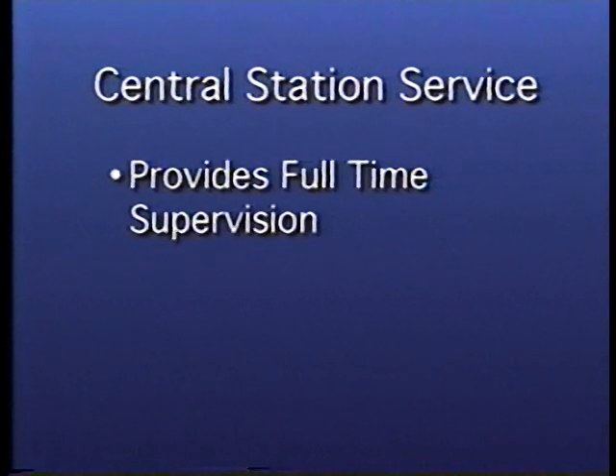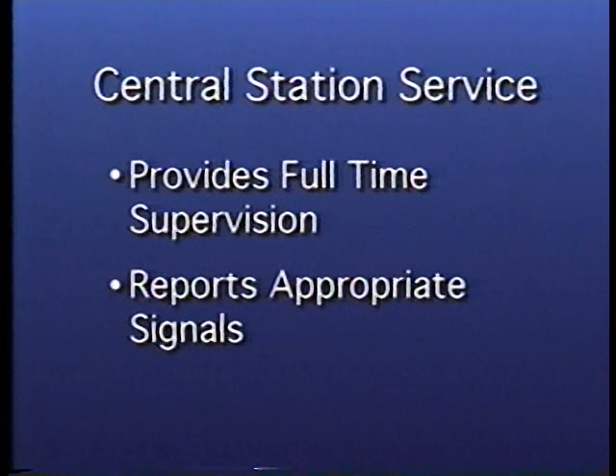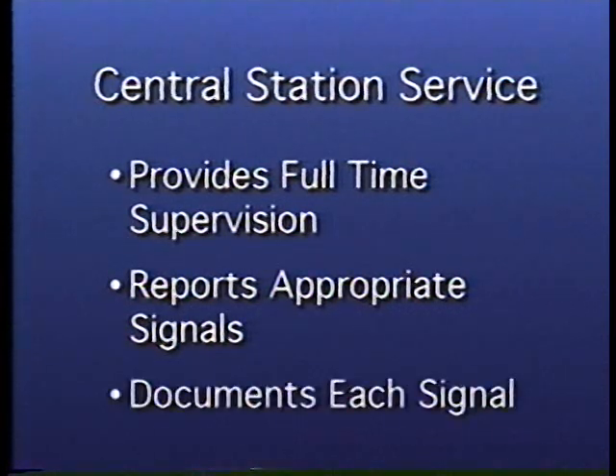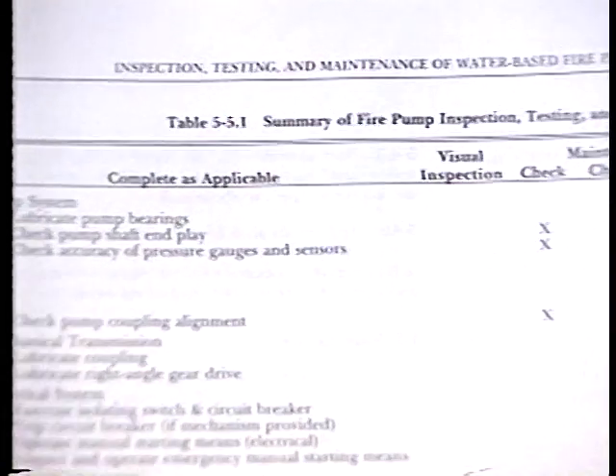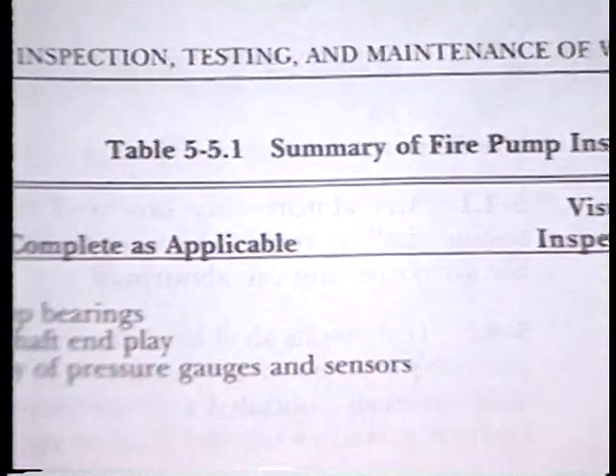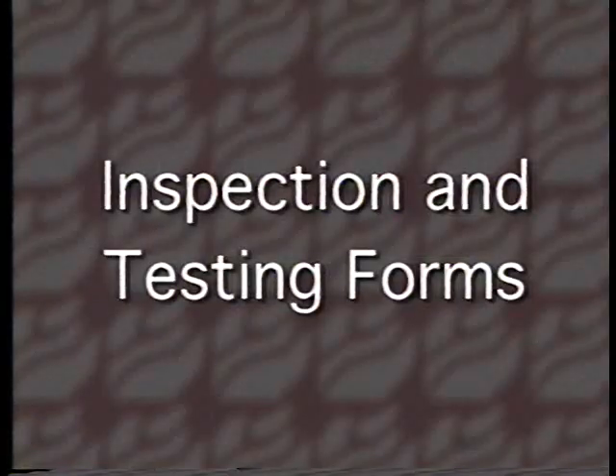In some cases, the local code will require such protection unless full-time service, equivalent to a proprietary protective signaling system, is provided on site. The Central Station Service provides full-time supervision of the system, notifies the local fire department and the owner of appropriate signals, and documents each signal. The fire pump inspection, testing, and maintenance schedule is summarized in Table 5-5.1 from NFPA 25.